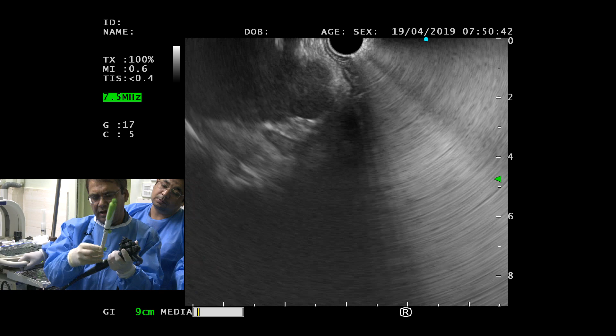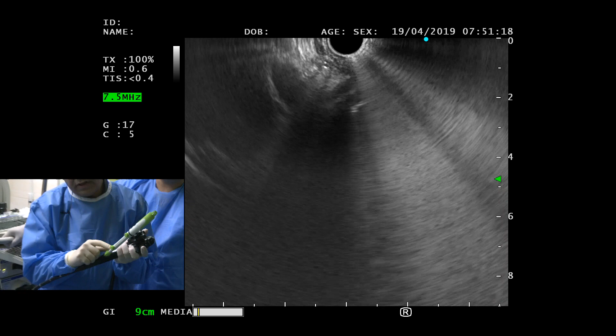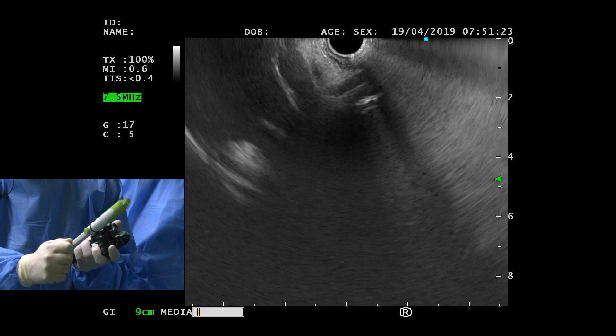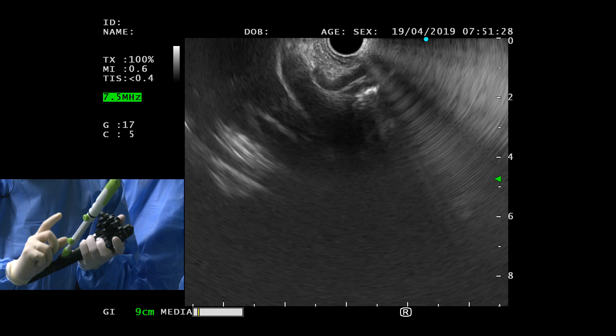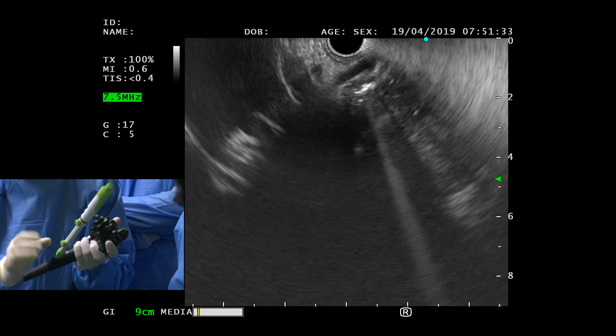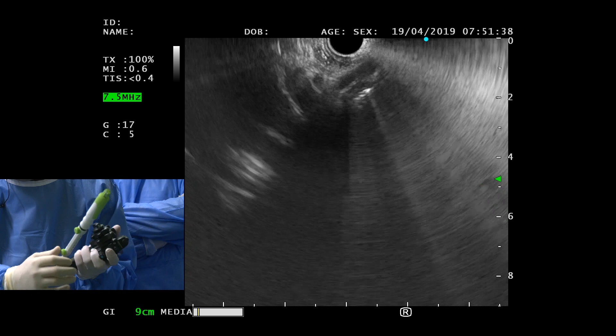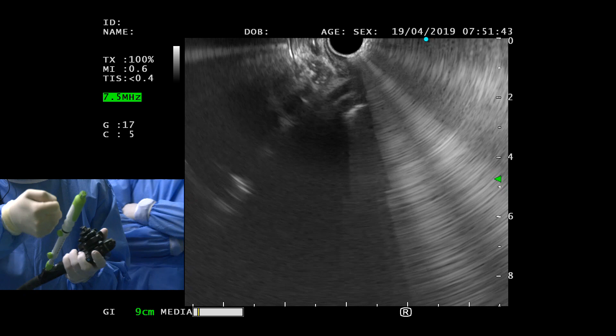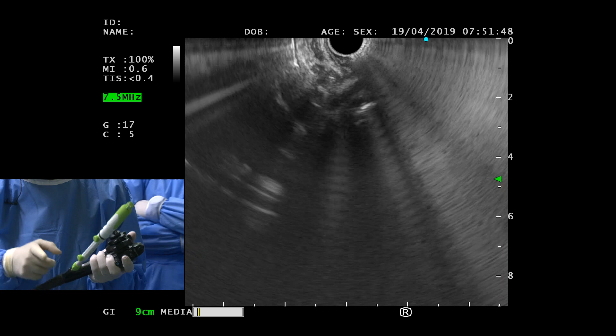So first, before you start, make those wheels or locks face towards you, and it really will take 75% of the turn, and they will be on your right side, and you can easily maneuver those. One other important thing to keep an eye on: this one usually comes fixed at 1, so try not to touch this. Once you open the sheath, you always have to adjust it before you can take the needle out. Sometimes you will have to adjust the sheath, but try to keep it locked the way it comes. If you open it once, make sure you lock it really tight, because when you do FNA and make a stab with the needle, you don't want the sheath to be stabbing the duodenal wall, okay?